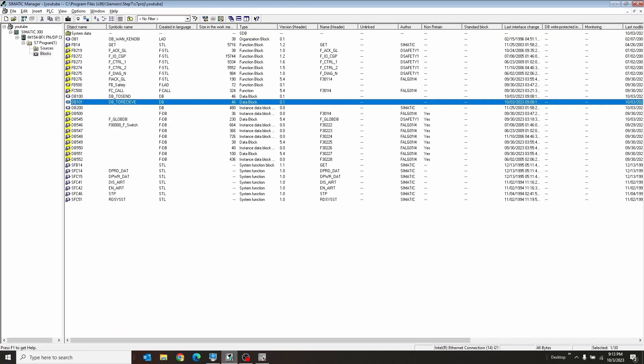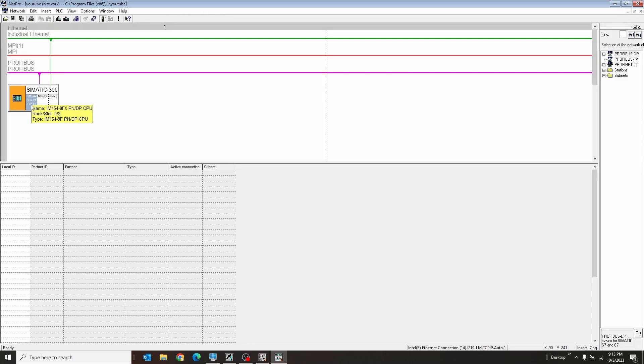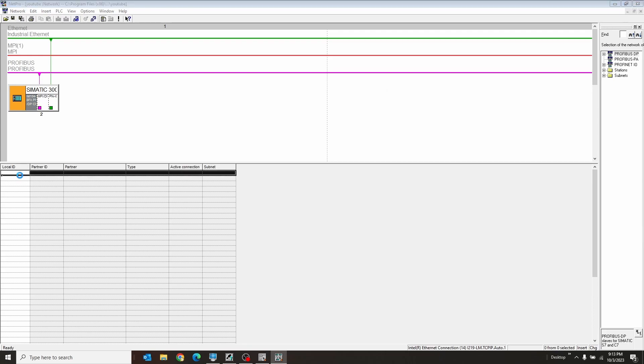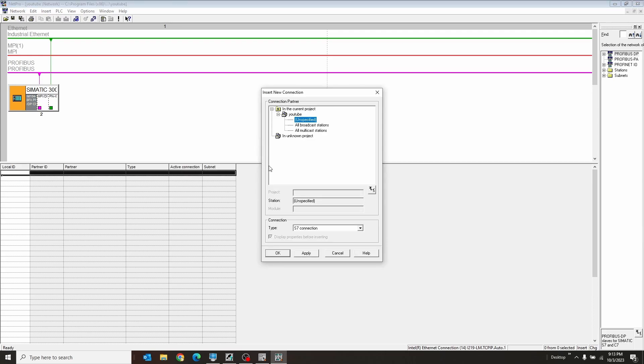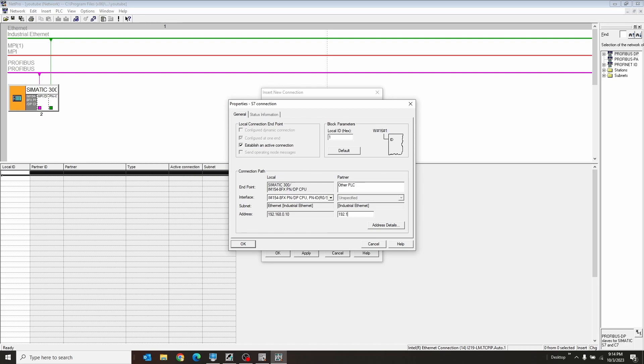We're going to go into NetPro, which is this icon up here. We're going to go down to our PLC, click under here, and we're going to double click on local ID to create a new connection. We're going to create an S7 connection. Now here is the important bits. Only one PLC has to establish an active connection. So our first PLC will have this checked and the other one will not. So our other PLC is going to be called other PLC. And we're going to give this IP address of the other guy, which in my case is going to be 0.50. They have to be in the same IP range. It can't be like 192.168.0.10 and the other one be like 171.10.0. They have to be in the same subnet family where just the last octet is different.